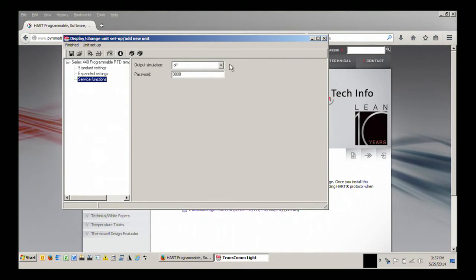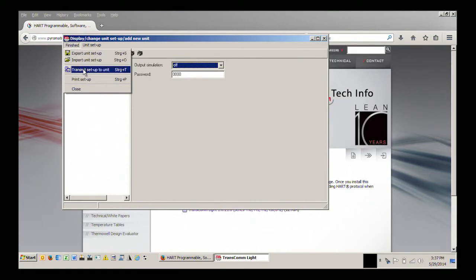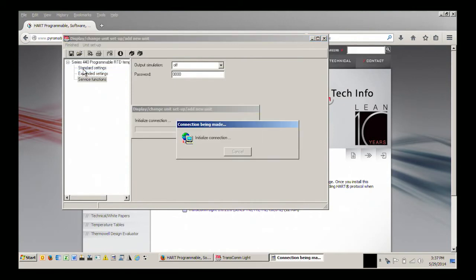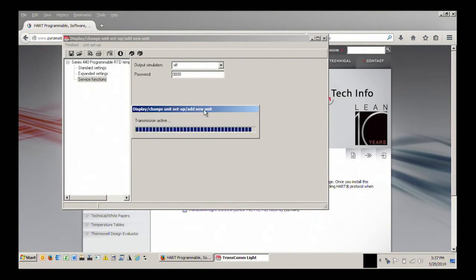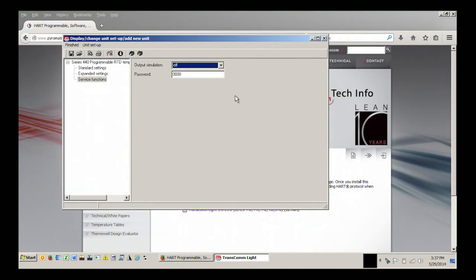The measurement point identification is just a text box that's saved for, like a calibration date or something like that. There's also in the service functions, the output simulation can be turned on. Once you turn this on, you can force a milliamp signal out of the device and you can troubleshoot anything down the line. There is a choice for a password to put in. Once you've done making any settings, you go to finished. And then you want to transmit setup to unit. And once the box goes away, you have completed programming the TransComm Light 440 transmitter.